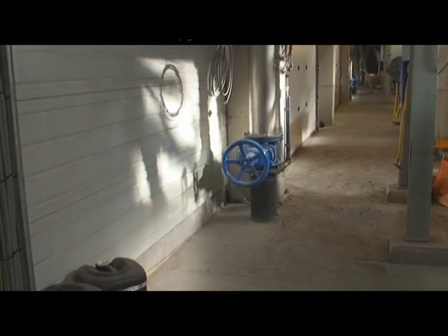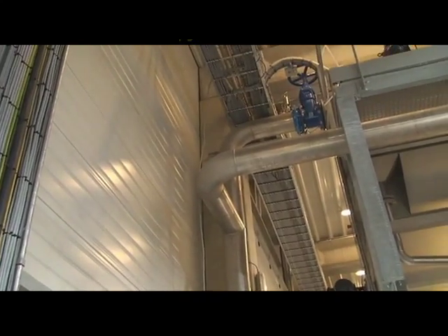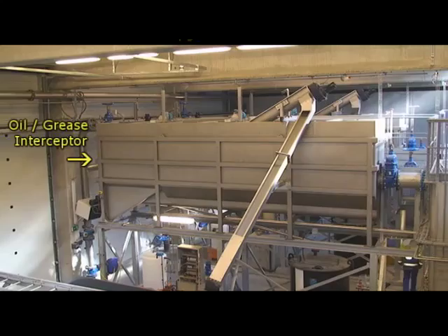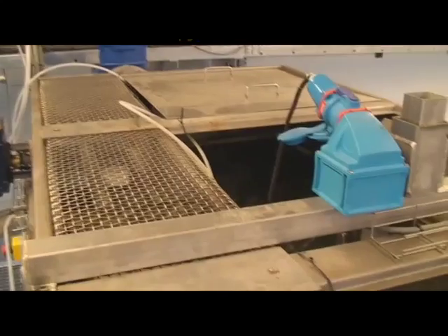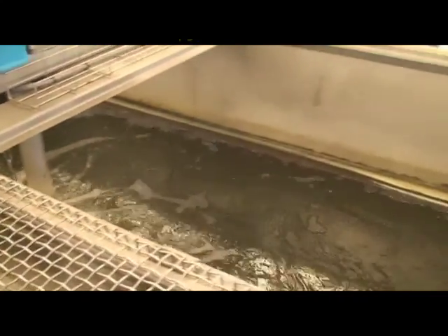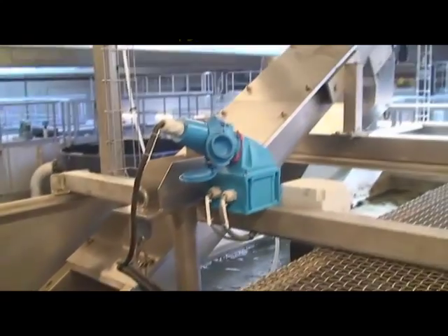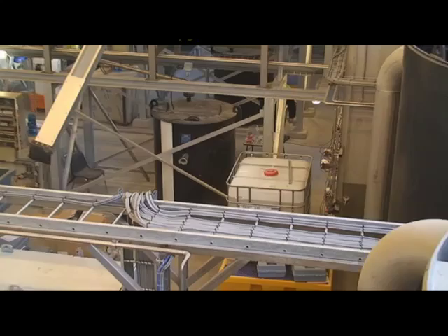The plant consists of three main lines, each capable of treating cooling tower makeup water for one-third of the critical capacity. A combination sand, oil, and grease separator receives the water as it enters the plant from the subgrade piping. Aerators are used to disturb the water during the separation process. A conveyor removes the sand from the fluid, and the suspended solids are skimmed off and deposited into containers to be recycled.